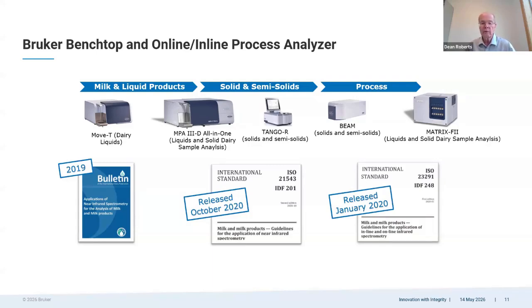The Beam is one of the inline analyzers that uses reflection spectroscopy, so that can be used for measuring high solids products like cream or cultured products and powders and cheeses in an inline analysis. And this is a single point analyzer. And then finally, the Matrix F2 is a 6-channel multiplexed near-infrared analyzer that's capable of measuring both liquids and solids.